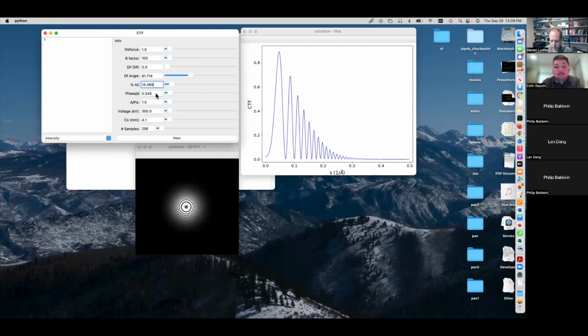So that's the traditional image formation electrons that you get. Then any electron that undergoes inelastic scattering, in other words, it loses energy when it scatters or gets scattered off in a funny direction, is considered to be sort of absorbed. So if you have an electron microscope that has an energy filter on it, the idea is that it's getting rid of all of those electrons that get scattered but don't have the right energy anymore. They can't form a proper image. If you don't have an energy filter, those things still wind up hitting the detector and they show up as extra noise. If you do have an energy filter, then they get eliminated completely. Okay, what does that mean? So any electron that you lose, that's what you'd normally term amplitude contrast. But that's not what cryo-EM means by amplitude contrast.